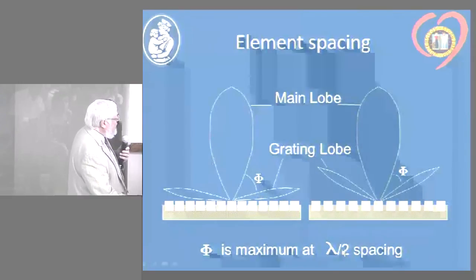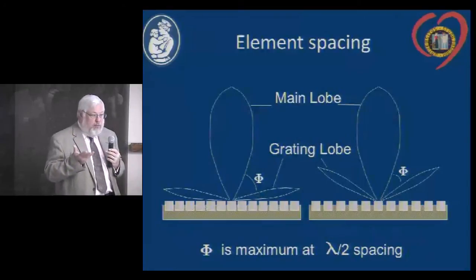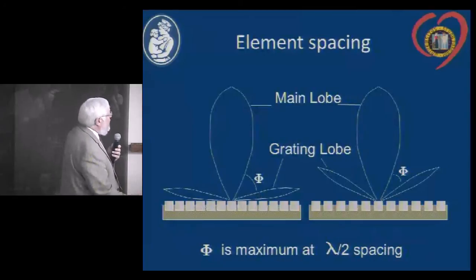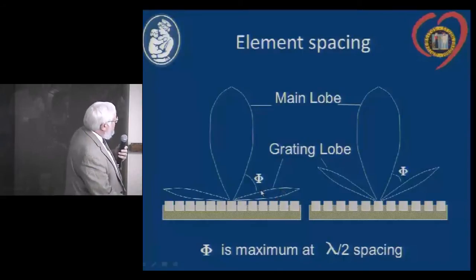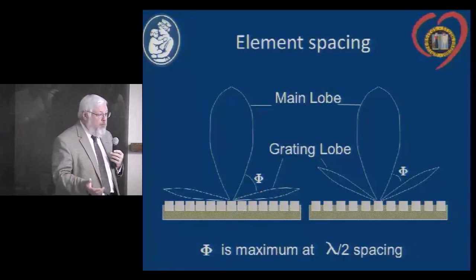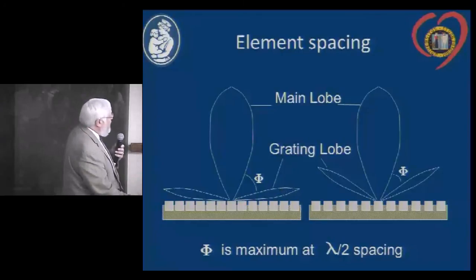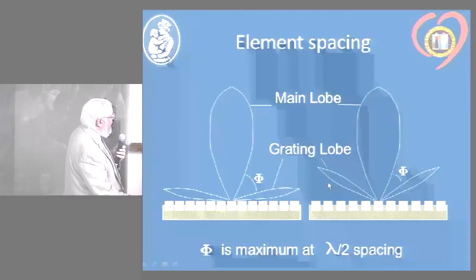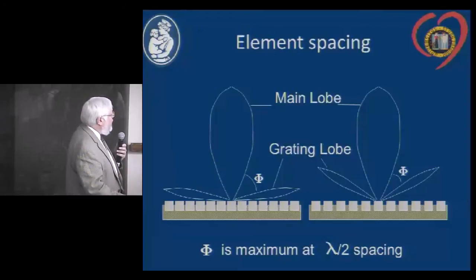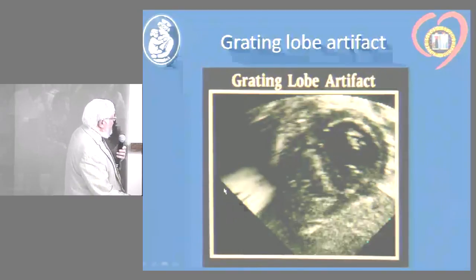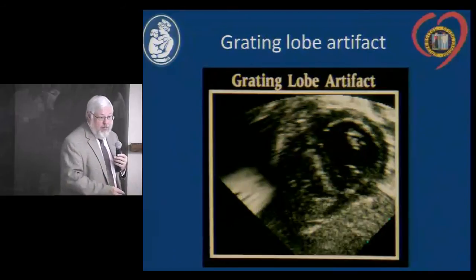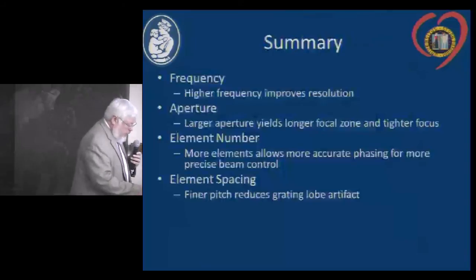At lambda-over-two spacing, the angle between the main beam and grating lobes is greatest, meaning the grating lobe artifacts are pushed further away. Grating lobes go off into space and create artifacts within the image. An example of a grating lobe artifact shows them occurring near the edge of the image; if a structure of interest were beneath one, you wouldn't be able to see it. So element spacing is important for 2D image quality.